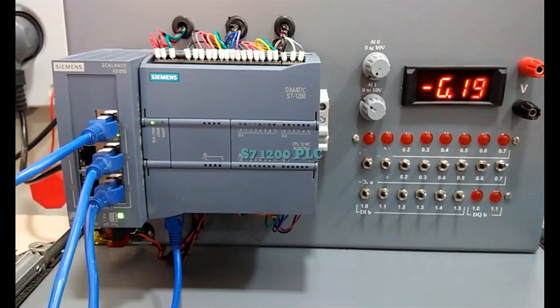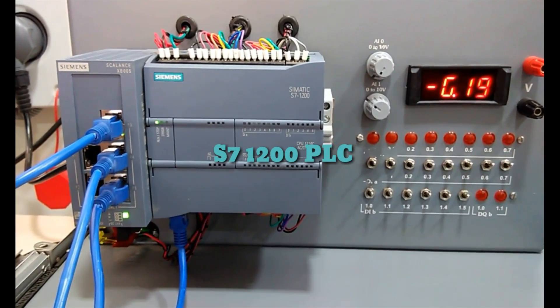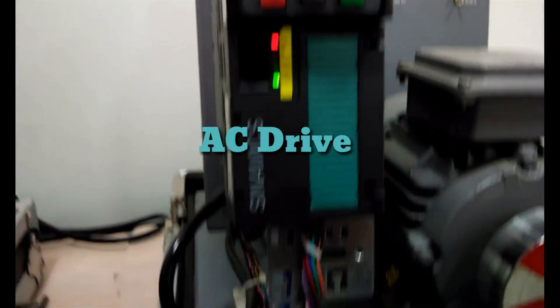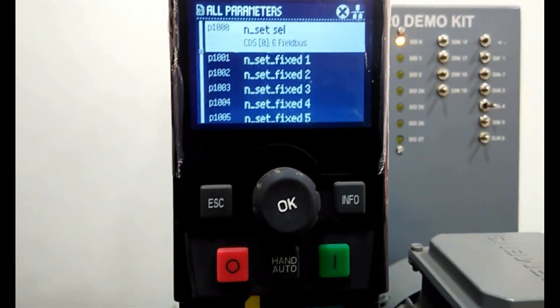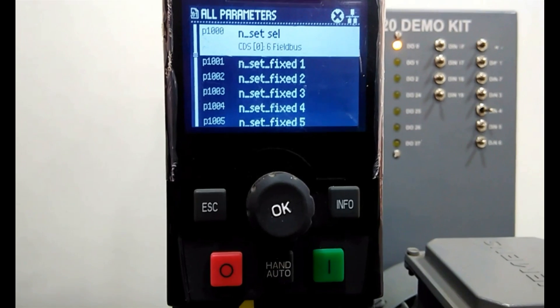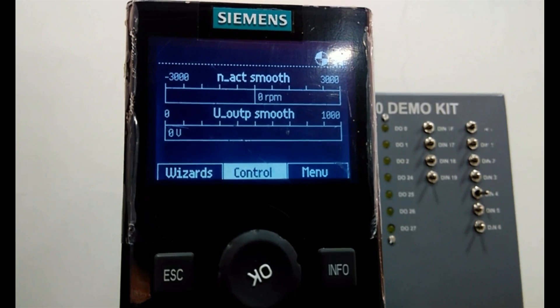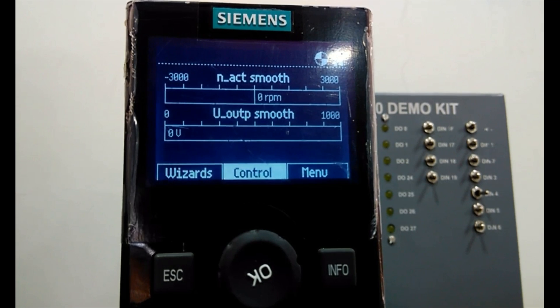Here you can see we have the Siemens S7-1200 CPU, and with this switch we have connected this G120 AC drive with this PLC. Downside, this PROFINET cable is connected with this switch, and from the switch we have connected this PLC and then the drive — that is mandatory for this communication. Now in this IOP we will enter the parameters that are mandatory for the communication between drive and PLC.